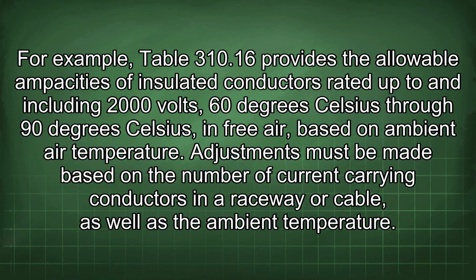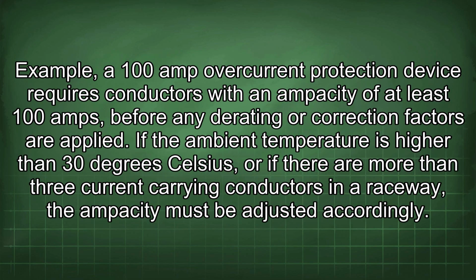For example, Table 310.16 provides the allowable ampacities of insulated conductors rated up to and including 2000 volts, 60 degrees Celsius through 90 degrees Celsius, in free air based on ambient air temperature. Adjustments must be made based on the number of current carrying conductors in a raceway or cable, as well as the ambient temperature. Example: a 100 amp overcurrent protection device requires conductors with an ampacity of at least 100 amps before any derating or correction factors are applied. If the ambient temperature is higher than 30 degrees Celsius, or if there are more than 3 current carrying conductors in a raceway, the ampacity must be adjusted accordingly.